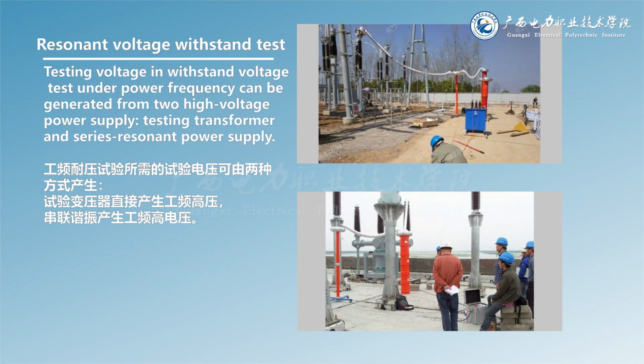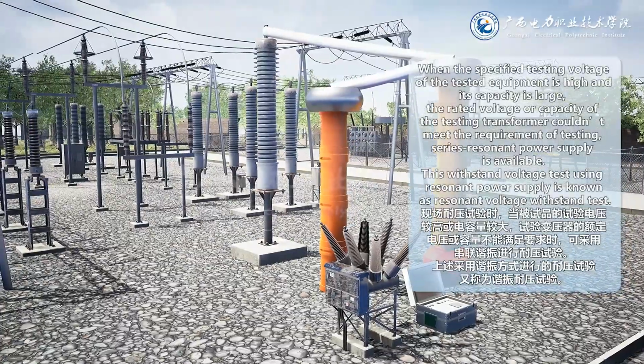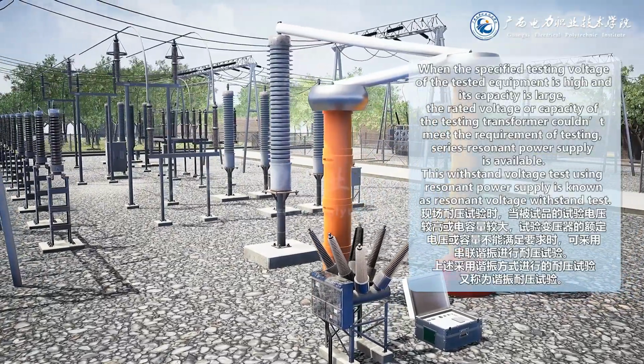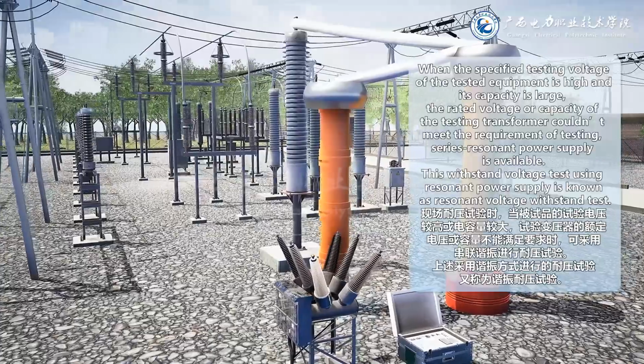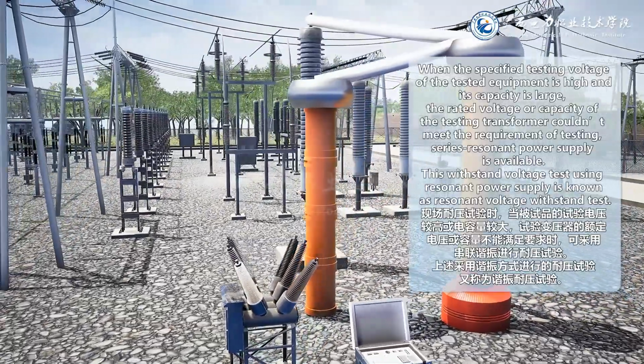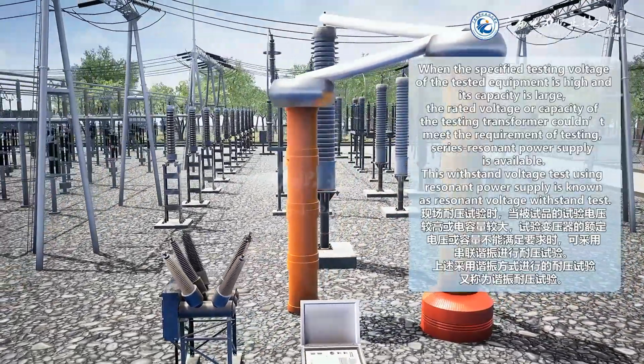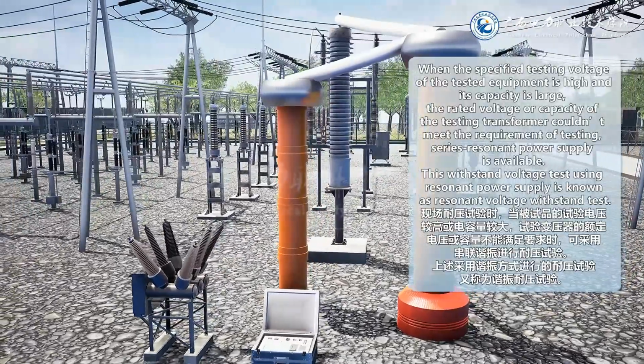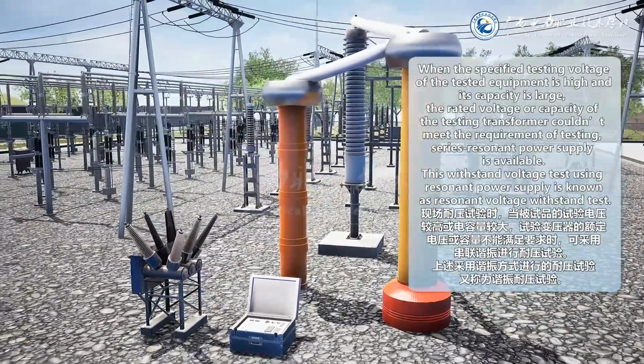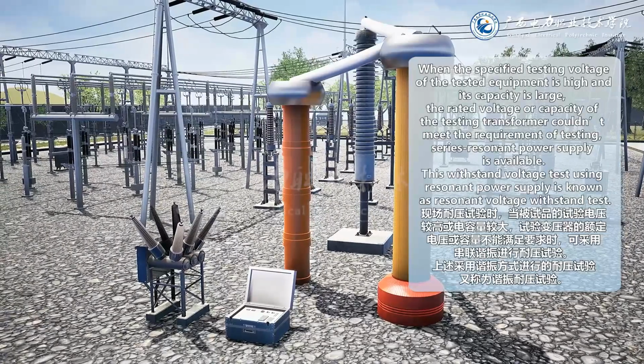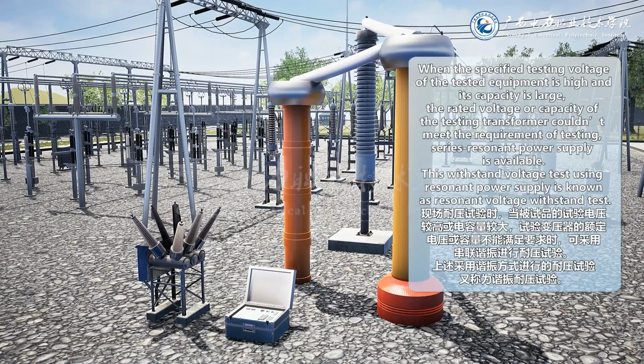Testing voltage in withstand voltage test under power frequency can be generated from two high voltage power supplies: a testing transformer and a series resonant power supply. When the specified testing voltage of the tested equipment is high and its capacity is large, the rated voltage or capacity of the testing transformer couldn't meet the requirement of testing, so a series resonant power supply is available. This withstand voltage test using resonant power supply is known as resonant voltage withstand test.